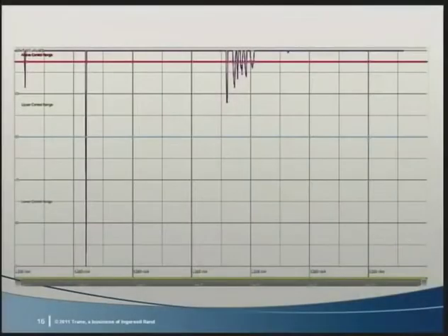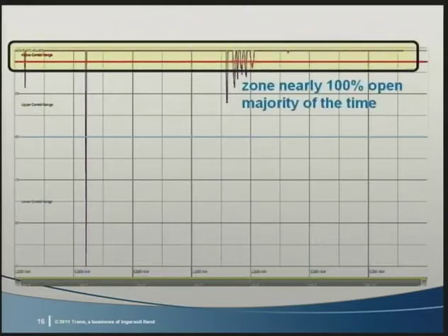The extra fan energy adds cooling load to the system through fan and motor inefficiency, which amplifies the energy saving opportunity. Here's a zone in a system scheduled on for every hour of the day. For some reason, this zone is not satisfied. The VAV box is starved. In this example, it is unable to meet the load with the maximum flow setting. It was rarely able to achieve the cooling set point of 62 degrees. Because the VAV box is wide open most of the time, it defeats the duct static pressure optimization algorithm.